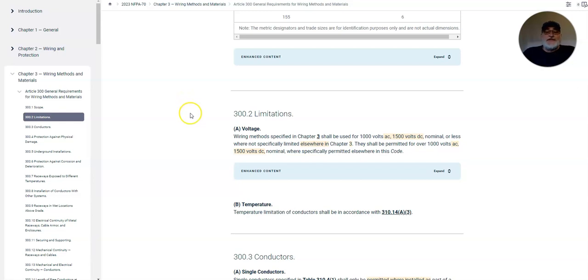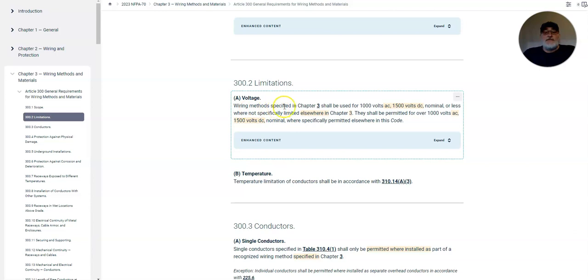We're going to go ahead to 300 part 2, the limitations. Voltage. Wiring methods specified in Chapter 3 shall be used for 1,000 volts AC, 1,500 volts DC nominal or less. Where not specifically limited elsewhere in Chapter 3, they shall be permitted to be over 1,000 volts AC and 1,500 volts DC nominally where specifically permitted in this code. Basically, Chapter 3 is going to be covering anything at 1,000 volts or less. Okay, that is what we're going to be considering. We are at medium or less than medium voltage when it comes to the trade, because we have lots of different voltage types going all the way up to transmission voltage, which is 144,000 volts, all the way down to 24 volts AC. Your doorbells could very well be wired on 12 or 24 volts AC in your house. That's what we're going to be covering here. That's what the limitations are.